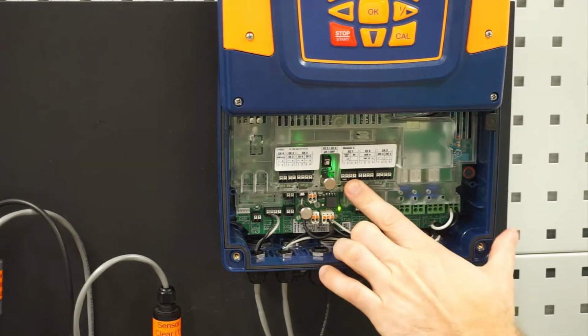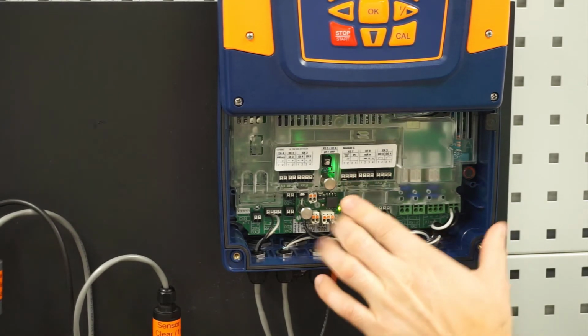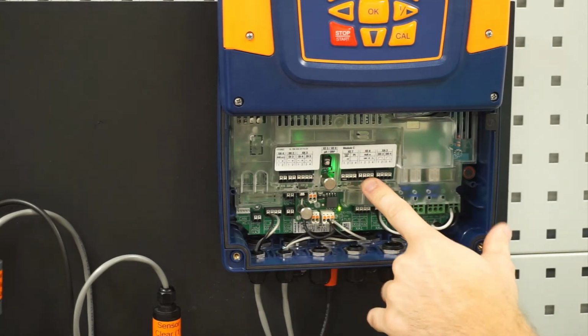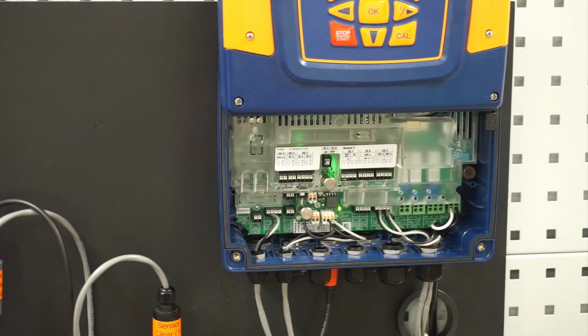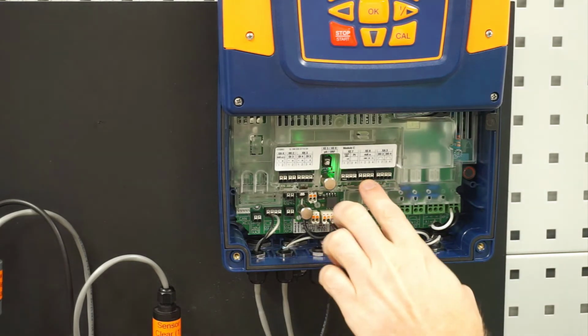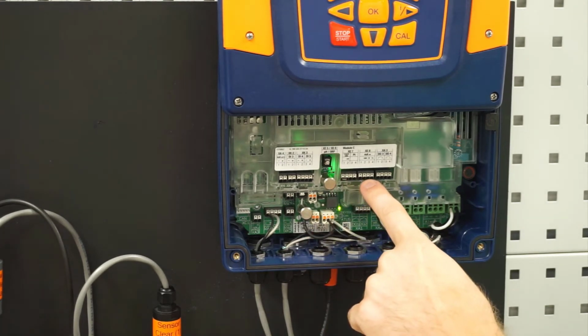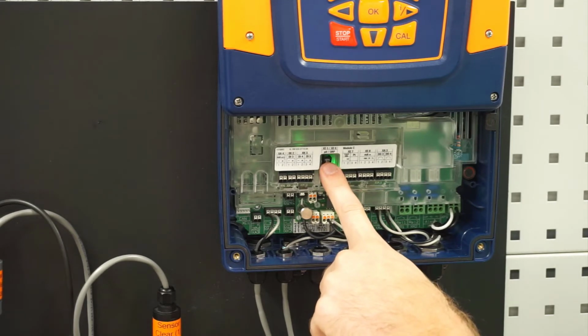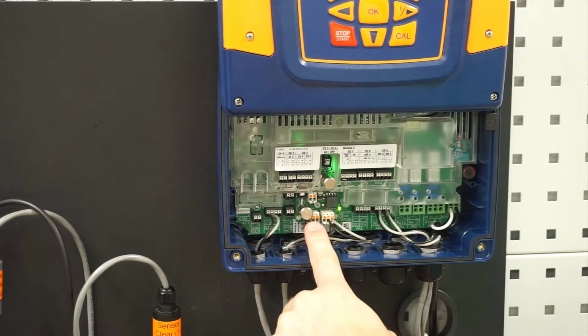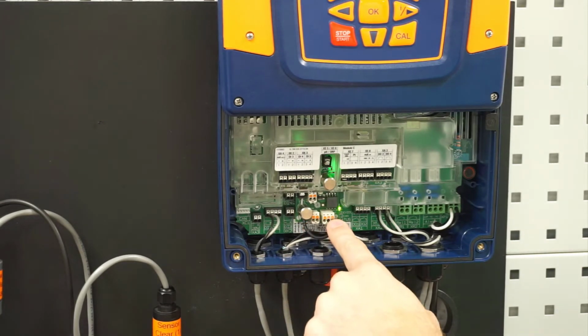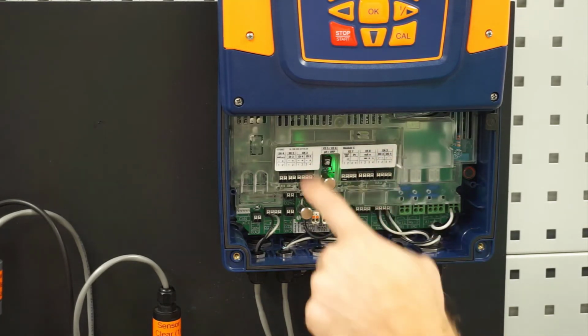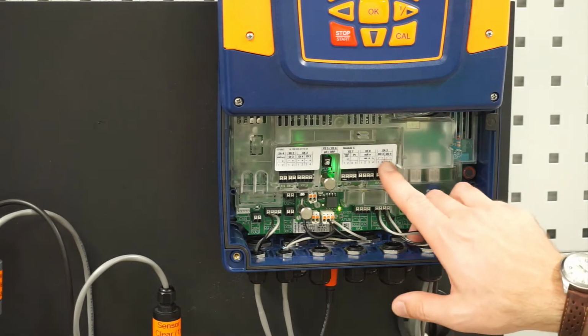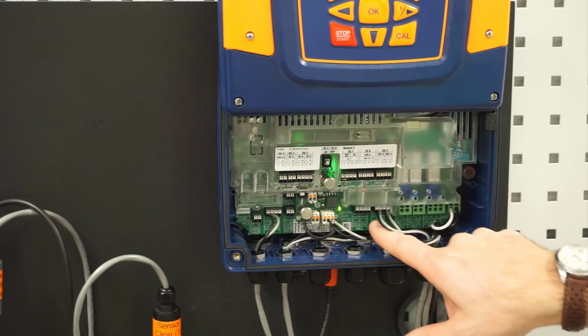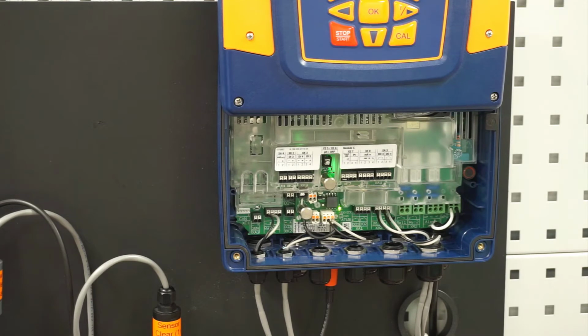Next to that, we have that liquid potential, another place for a temperature sensor like we have down here, and then next to that we have a milliamp input. So we could potentially bring in another amperometric sensor like total or free chlorine, peracetic acid, chlorine dioxide, chlorite, hydrogen peroxide. Those are options to go in there. One thing I will tell you is that I can only use one of these options. So if I have an amperometric sensor up here, I cannot have a pH sensor or an ORP sensor. This is a 3-channel controller. Down here is channel 1 with our pH, channel 2 with our free chlorine, and then channel 3 is up here, and we can only utilize one of those. And then to the right of that are those digital outputs that I already mentioned. So you have 4 digital outputs that would be for contacting out to potentially a prominent pump.